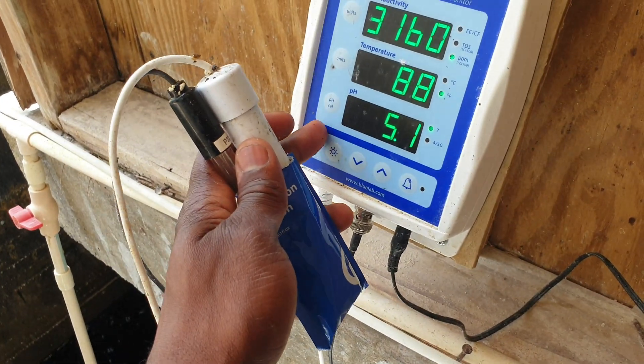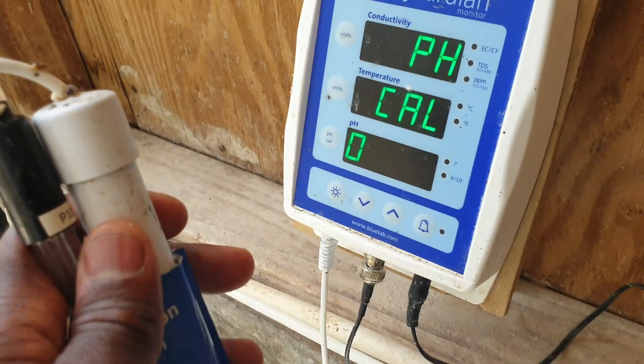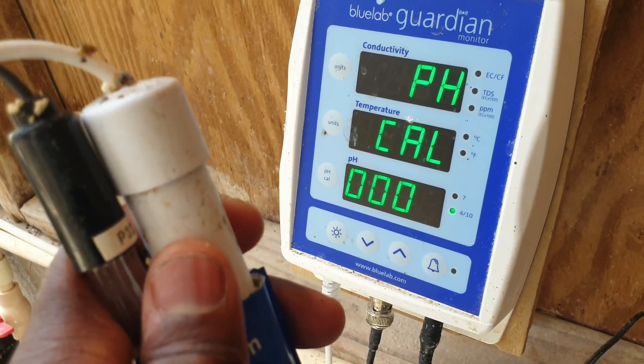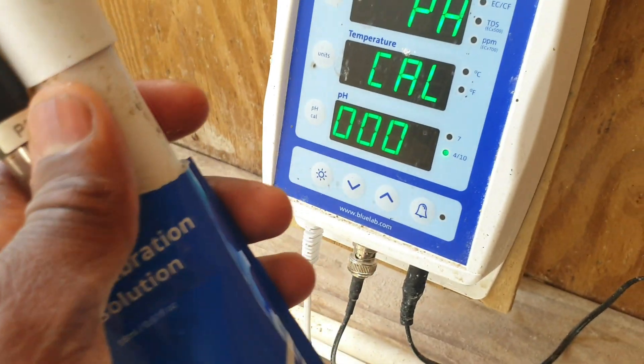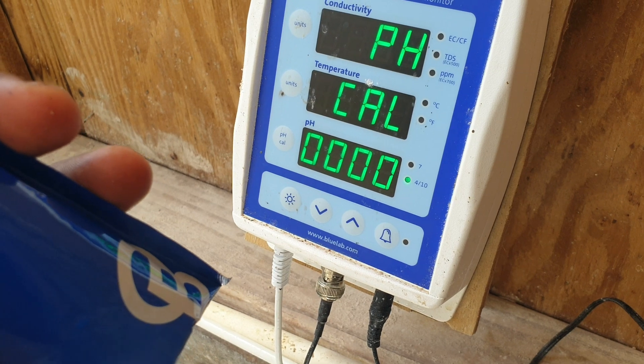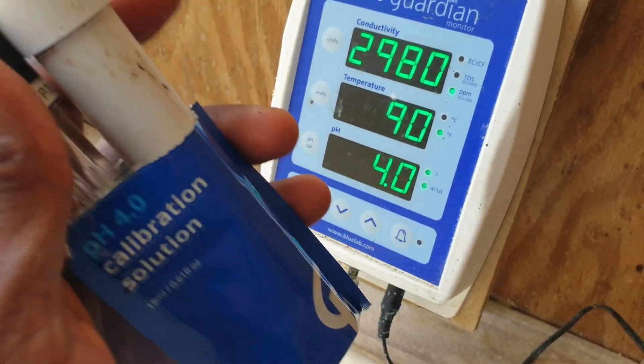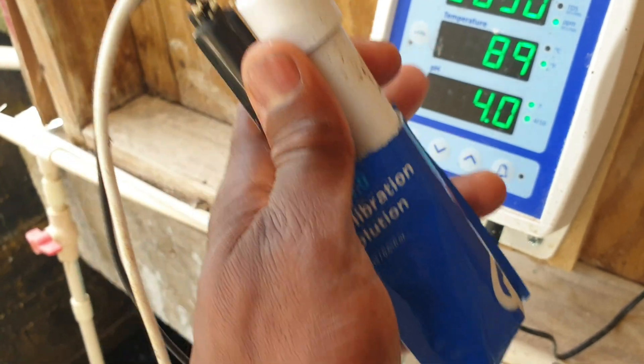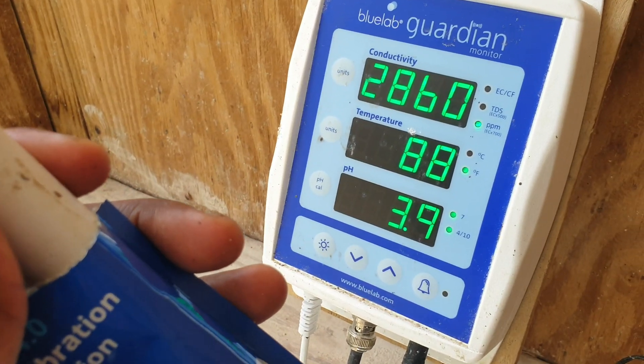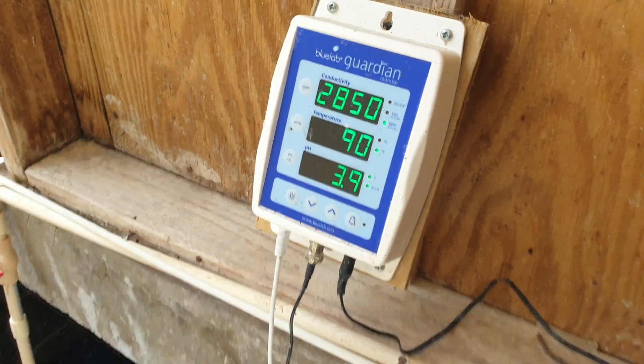I'm going to hold the pH CAL button again until it says 'pH CAL', then let go. It starts cycling through the zeros — it's supposed to cycle through four zeros. As you can see, the pH 4 LED is blinking as we use the pH 4 solution. Ensure that the pH probe — the transparent one — is in contact with the pH solution, because if it is not, the cycle through the zeros will take longer. The pH 4 LED light has now stopped blinking.